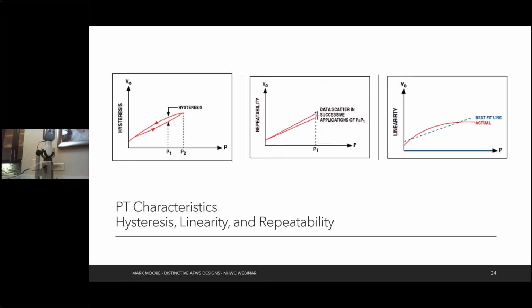Repeatability is pretty straightforward. It just says if we do the test again and again and again, do we get the same answer? We hope yes, but it's never going to be 100% perfect. Linearity says that we are applying a slope and offset equation from our Algebra 1 classes back in high school. So we're assuming that the PT has a straight line between its pressure and its voltage output or its SDI12 output or whatever it happens to be. This is never really the case. It's always slightly not linear, but we want it to be as close to a straight line as possible. For all of these conditions, if you remember, the 0.1% full scale error was taking all of these under consideration. So when we do calibrations and we're expecting it to get within 0.1% of full scale, it's accounting for this hysteresis and the fact that it's not perfectly linear. And so all of that's included in the error already.